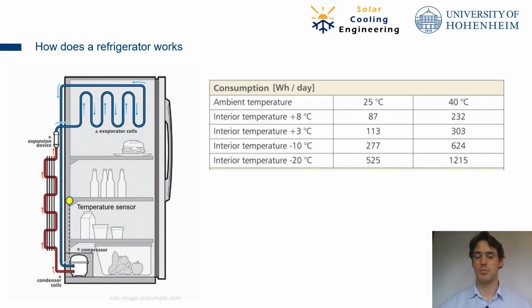If you go, for example, to minus 20 degrees with an ambient temperature of 40 degrees, you see a huge difference compared to just cooling products to 3 degrees at 25 degrees ambient temperature. This information is normally related only to the thermal losses.